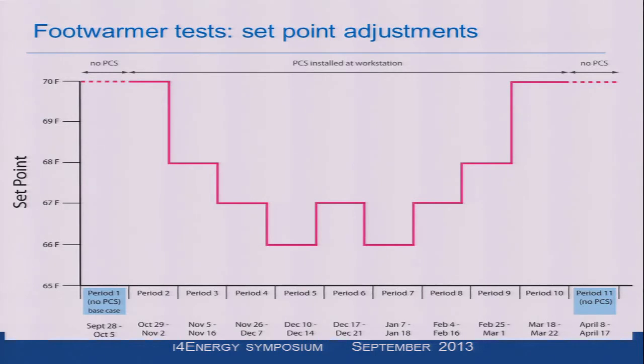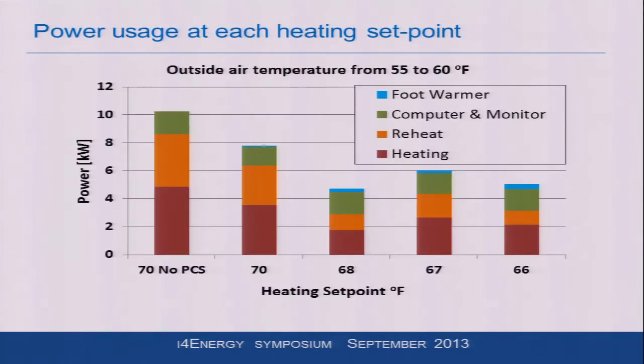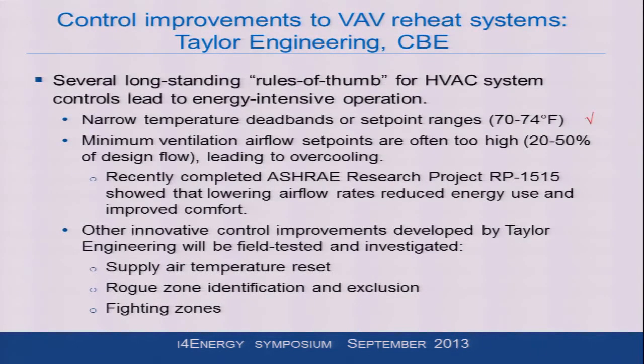And in this case, this was a winter test. We set the temperature down to 66 degrees and then back up to 70 where it had been for the previous 5 or 10 years fixed. And we get these big savings out of the test and the various changes made in the tests. It's 20 or 30% savings. So that's the potential, and I think we'll see this on the cooling side too. The hot weather is coming and the tests are about to be made for the cooling part of the system.